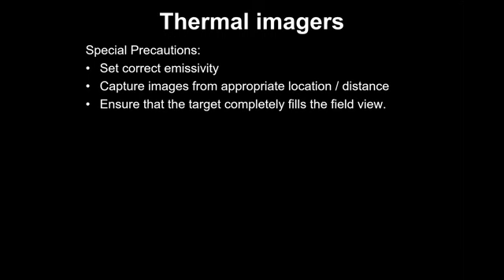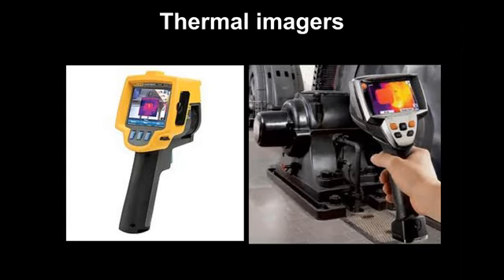Basically, the precautions are not much you need to do. Emissivity has to be correct, and distance should be correct, because the thermal imager has a limit on the distance. You cannot take it from 6 meter or 5 meter or 10 meter distance. So you have to maintain that distance. These are the thermal imagers, very handy instrument, and they are available, I'll tell you, from 25,000 rupees to 10 lakhs. Now they are available from a good company, Flir, as an attachment to your mobile. So you can connect it to the mobile and click. It has an app, so you install that app, connect that device, and you can record an image, you can video record the profiling of the temperature, and it has a range of, I think, 150 degrees. I have that instrument and I use it.